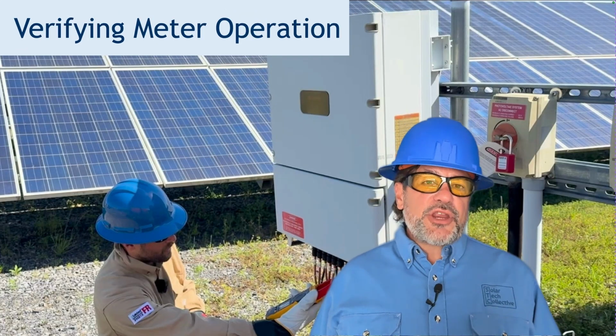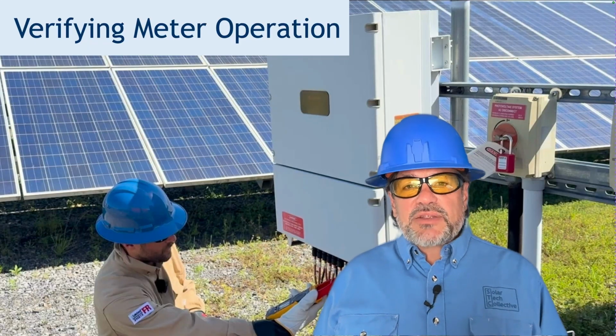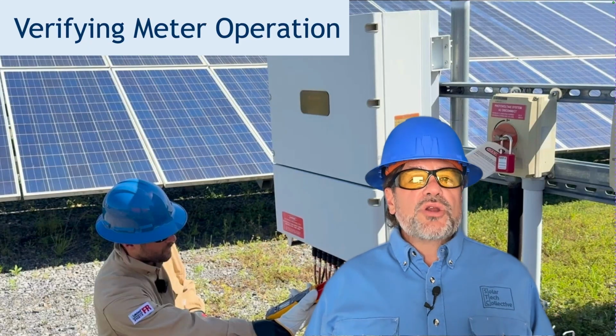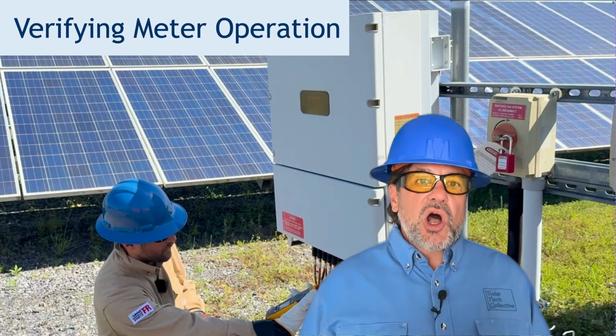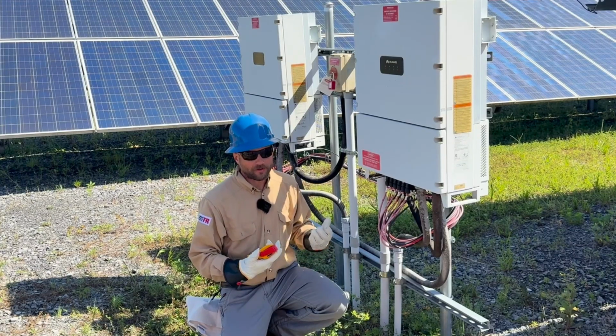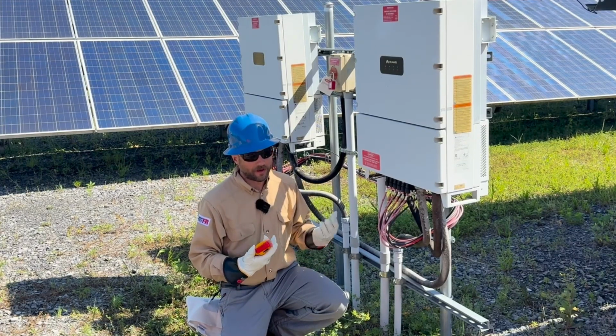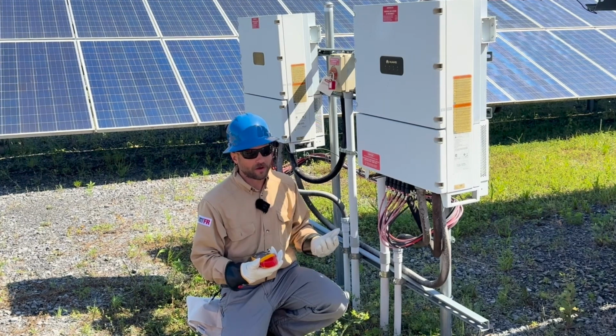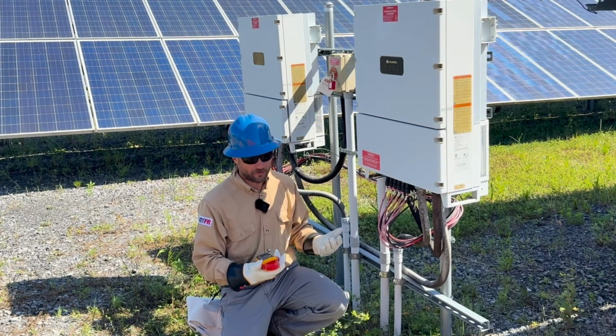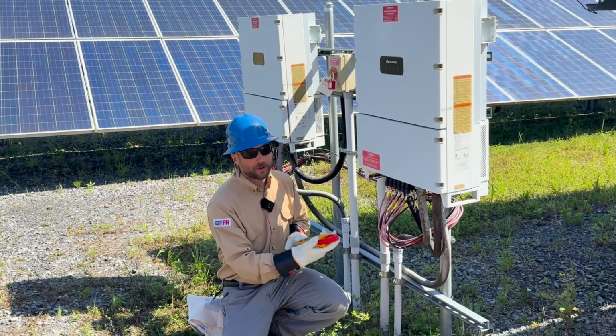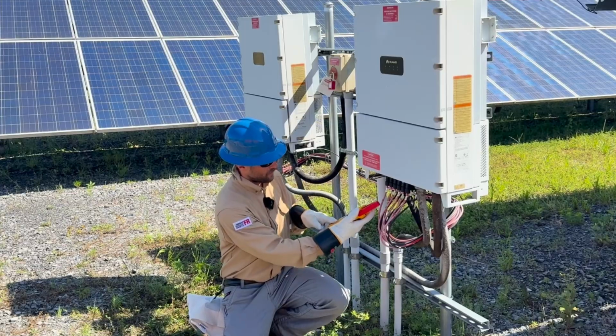Let's go ahead and take a look at a video from the field of verifying correct meter operation before testing for a lack of current on a circuit. Before we do any testing on the inverter that we're troubleshooting that has the issue, let's verify that our meter is operating correctly by testing current on an inverter that is operating at this very moment. First step, let's zero out our multimeter.